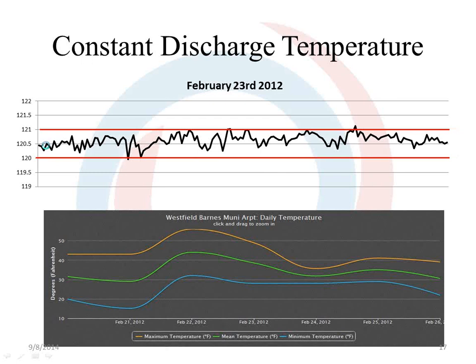Now, a little bit about the performance. On average, it's about 93%. But if you have discharge temperature set at 70 degrees, that efficiency goes to 98%. And I might add that 98%, there's no electrical savings involved in that 98%. We'll talk a little bit more about the electrical savings.